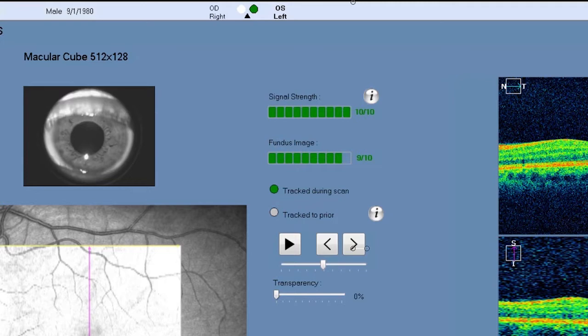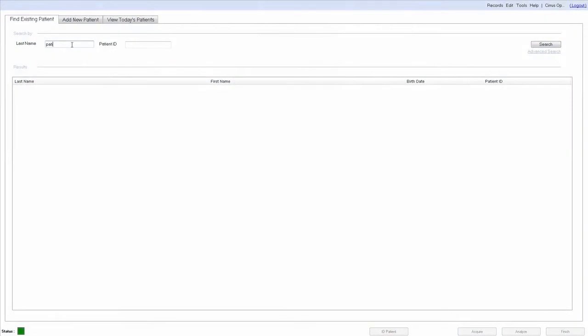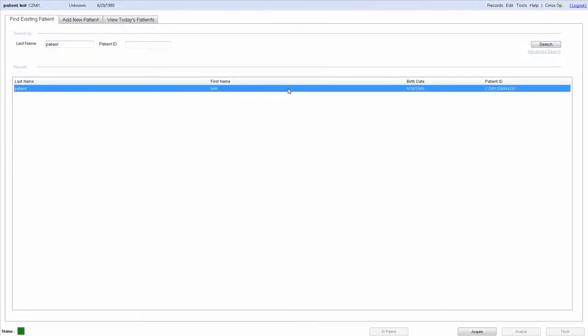There is also a quality rating for the fundus image. A fundus image quality score of 6 or above confirms that the quality is satisfactory. To begin your scan, select a patient and click on Acquire to go to the Acquire screen.